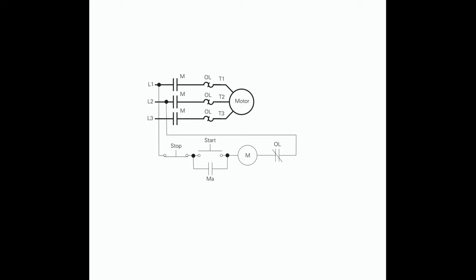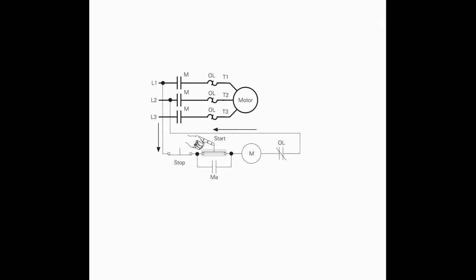Motor Starter Example: The following example involves a motor start and stop circuit. The line diagram illustrates how a normally open and a normally closed push button might be used in a control circuit. In this example, a motor starter M is wired in series with a normally open momentary push button (start), a normally closed momentary push button (stop), and the normally closed contacts of an overload relay (OL). Momentarily depressing the start push button completes the path of current flow and energizes the motor starter M.